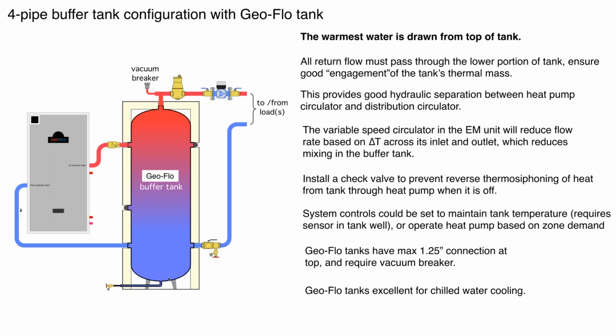Now, Enertech does have a buffer tank for sale, and it's a nice tank. I've actually used this tank in a project with water-to-water geothermal, and it is a polypropylene tank. This pressure vessel right here is made out of polypropylene, and it is wrapped with a fiberglass layer, and that provides the pressure shell, if you will, for that polypropylene. And then the whole thing is foamed, and there's a polypropylene jacket on the outside. So literally, it's a non-metallic tank. There's no corrosion concern with it. And it's a very well insulated tank. If you're dealing with chilled water, I found that it really is a well-built tank.